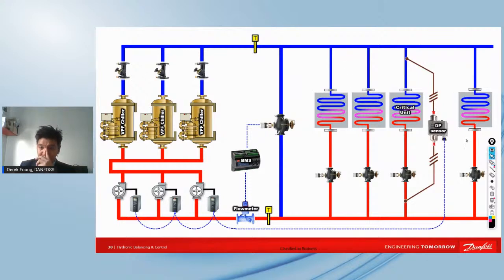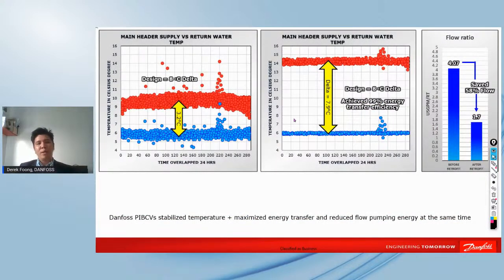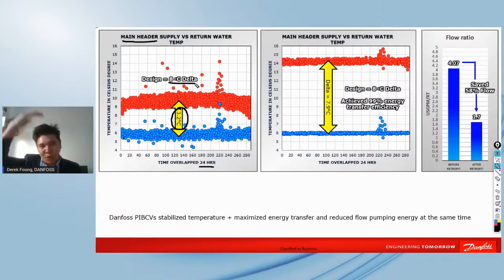So right here, when we dive deep into the analytics, the very first thing we look at is the data of one month across the main header, and this is what we see. We overlap 24 hours and a month. Whenever we pick up this data, we saw a delta of about 3.2 Celsius, which is way below the 8 delta. It's about 40% right now, so there's a huge gap there. And once we replace hundreds of valves in this system and stretch it, we get about 99% close to the design delta.